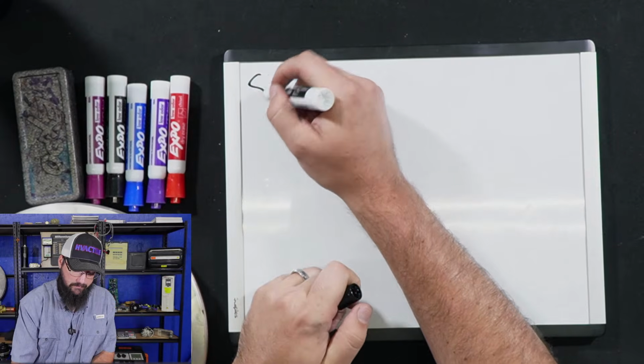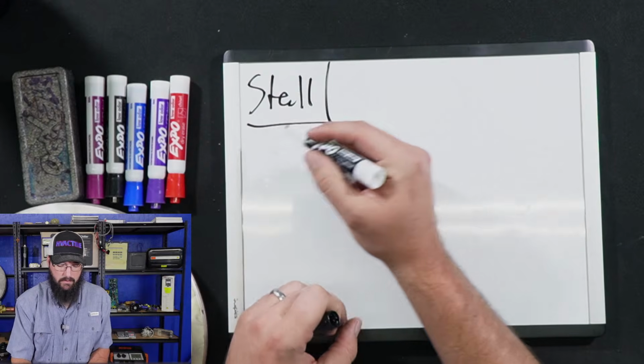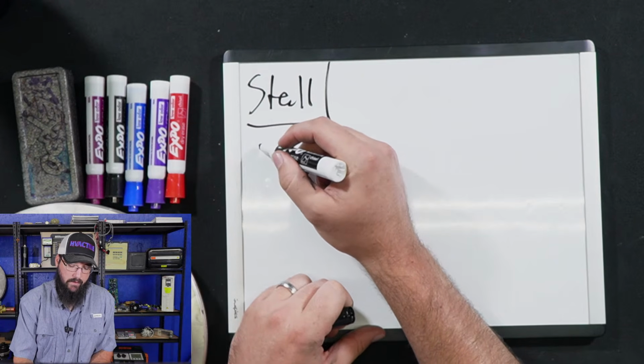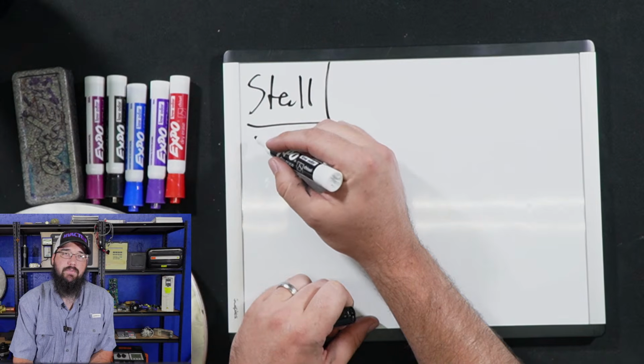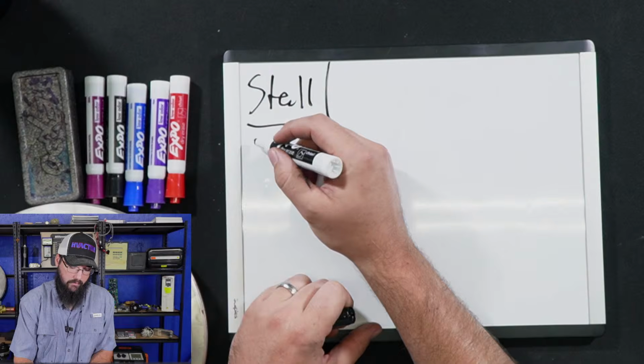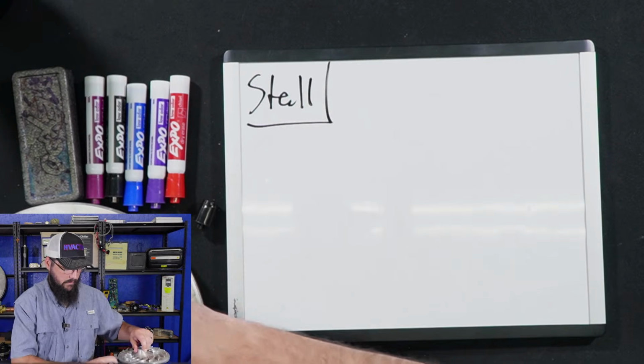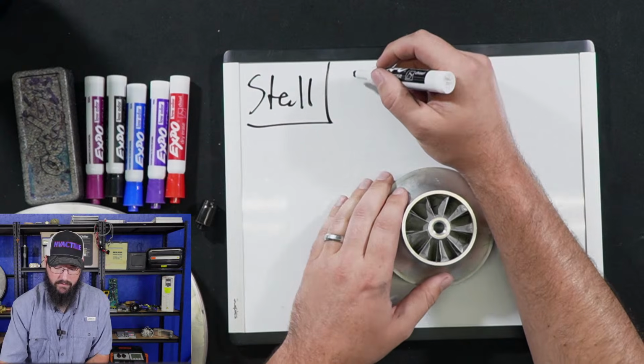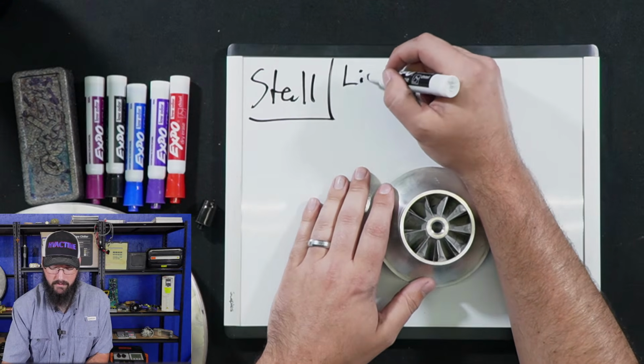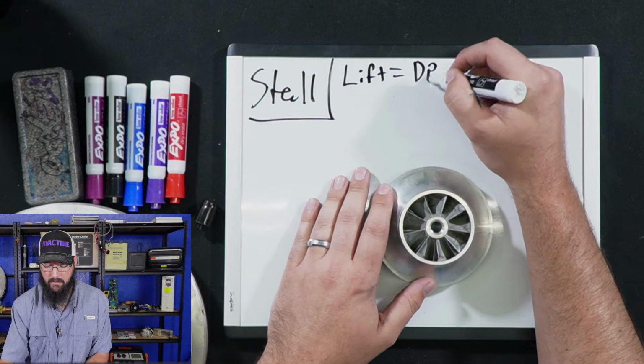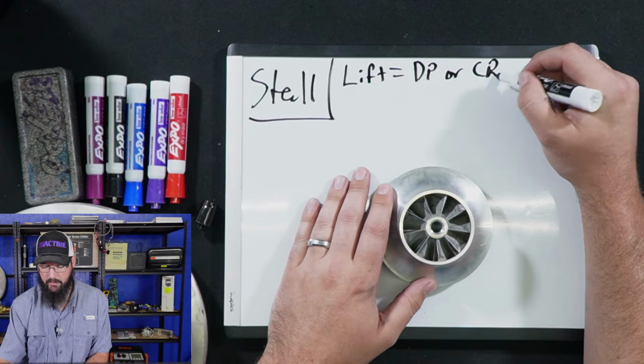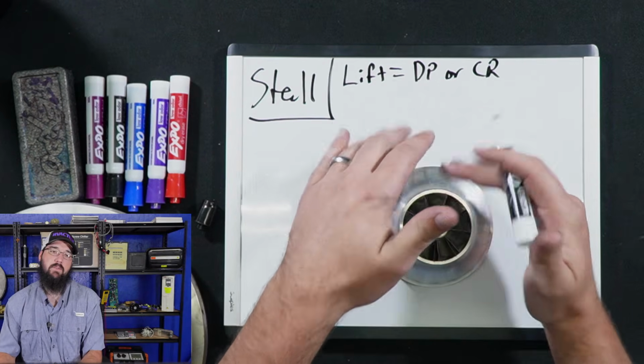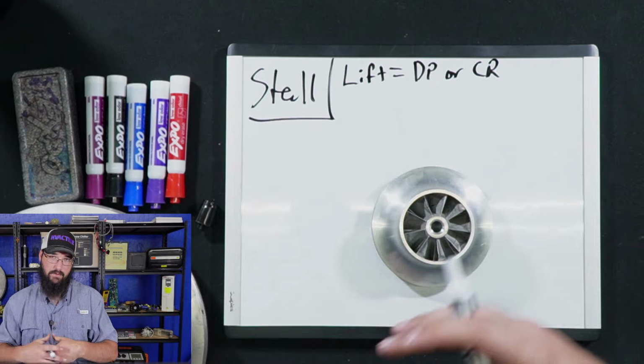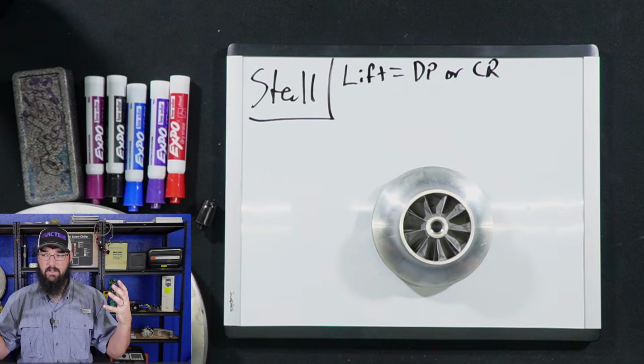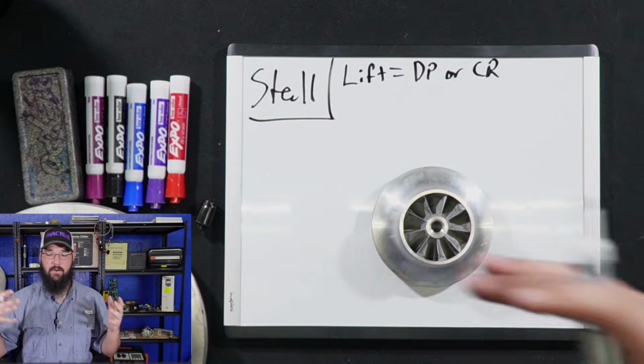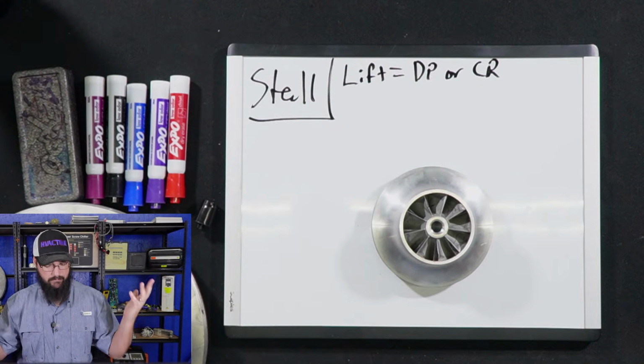Okay, so with stall, basically, we get to a condition where the lift becomes higher than we can push it through the impeller. By lift, you think of it as dP or compression ratio. So lift equals dP or compression ratio. I'll say CR, right? Same basic thing, we're just looking at it differently. So by lift, we're saying the pressure difference between evaporator and condenser is X number, 50, whatever.